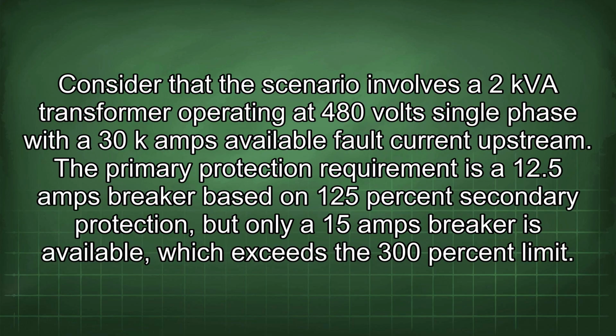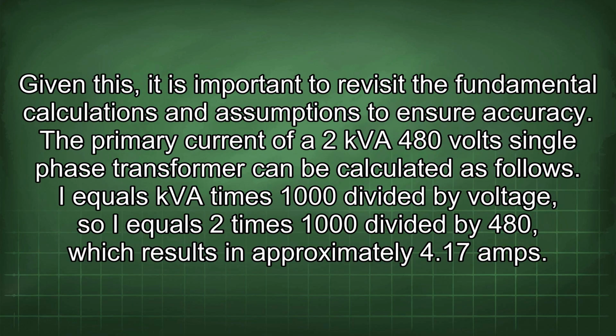Consider that the scenario involves a 2 kVA transformer operating at 480 volts single phase with a 30 kA available fault current upstream. The primary protection requirement is a 12.5 amps breaker based on 125% secondary protection, but only a 15 amps breaker is available, which exceeds the 300% limit. Given this, it is important to revisit the fundamental calculations and assumptions to ensure accuracy.